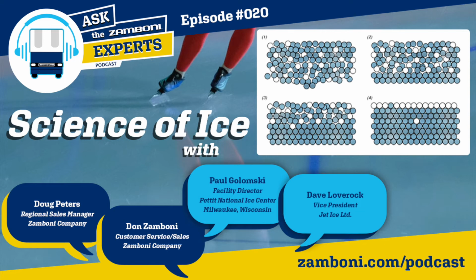I think a lot of that has to do with your air-ice interface temperature and the texture of the ice more than anything. And that's usually the texture of the ice isn't always reflective of mineral content or purity, whether it's DI or RO. It's reflective of the temperature of the slab itself. A lot of the figure skating events we do, we're running air-ice interface temperatures of 26, 27, 28. It gives them a softer texture.